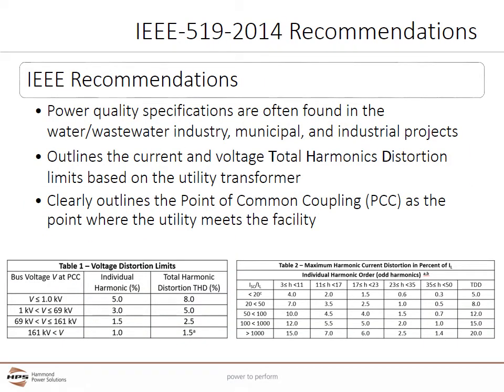IEEE 519 is recognized as the American national standard and is widely used in North America, especially in municipal public works markets. This standard details the recommended practices and requirements regarding harmonic control in electrical power systems. It outlines the current and voltage total harmonic distortion, or THD, that are recommended based on the input transformer's characteristics and the loads in a customer's facility. The current THD limits set by IEEE are clearly outlined in the tables. The point of common coupling is defined as the point of connection between the utility and the customer. IEEE 519 limits systems at less than 1,000 volts to 5% total harmonic distortion of the current.